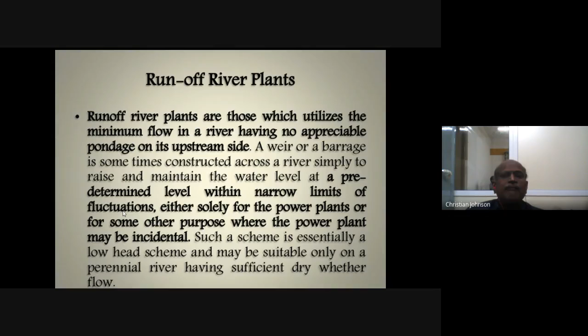A weir or barrage is sometimes constructed across a river simply to raise and maintain the water level at a predetermined level within narrow limits of fluctuation, either for the power plant alone or for some other purpose where power generation is incidental. Such a scheme is essentially a low-head scheme and may be suitable only on a perennial river with sufficient dry weather flow.